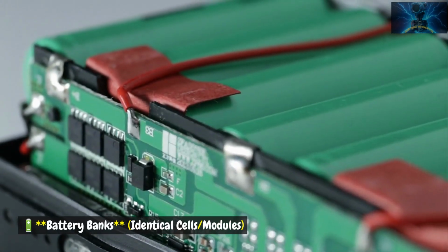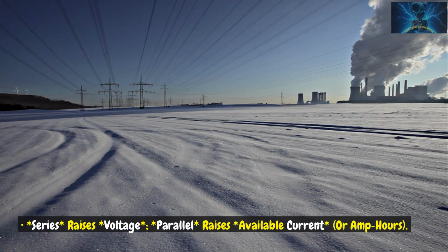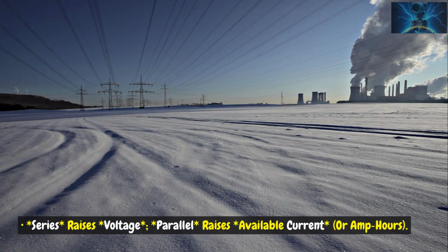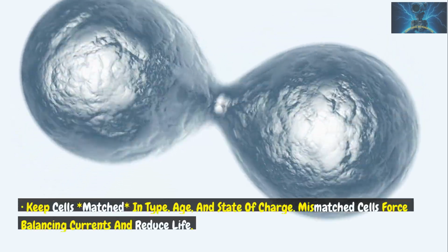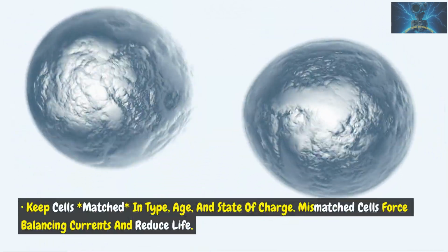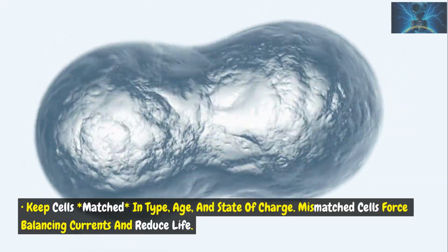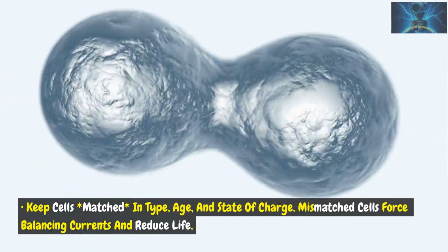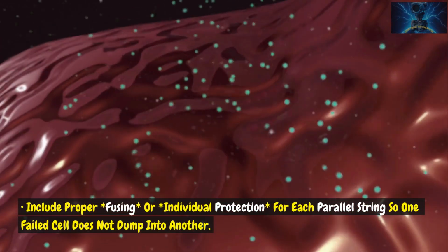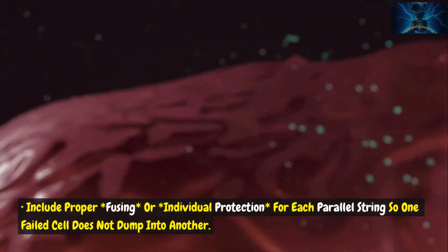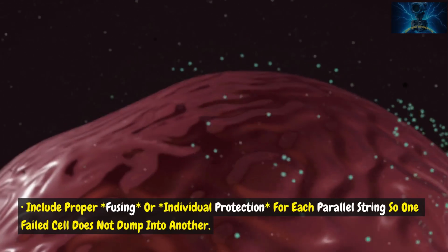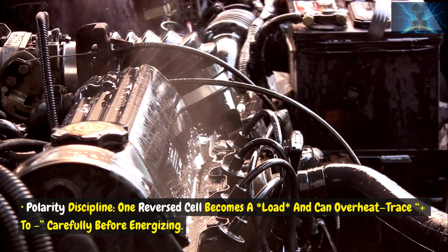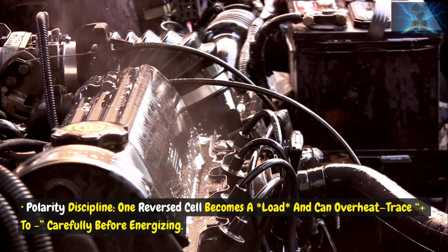Battery banks, identical cells or modules. Series raises voltage, parallel raises available current, or amp hours. So keep cells matched in type, age, and state of charge. Mismatched cells force balancing currents and reduce life. Include proper fusing or individual protection for each parallel string so one failed cell does not dump into another. Polarity discipline: one reversed cell becomes a load and can overheat, so trace polarity carefully before energizing.